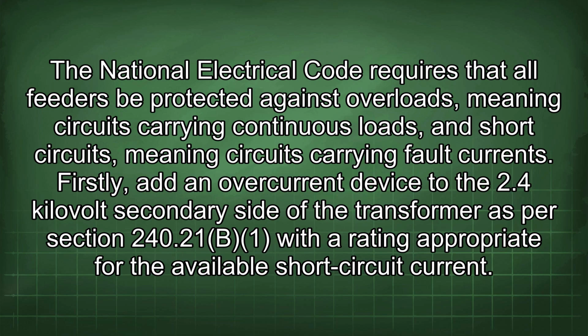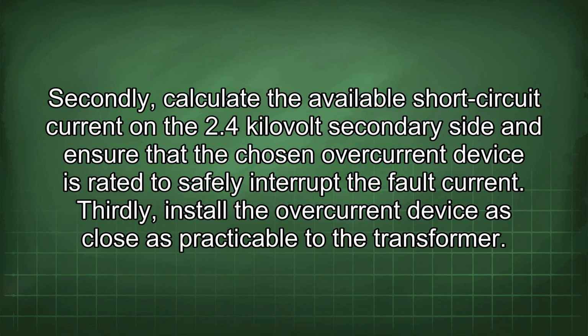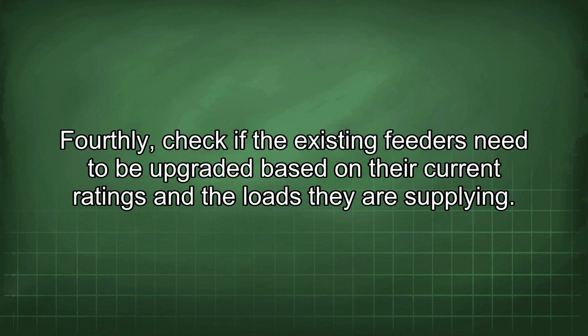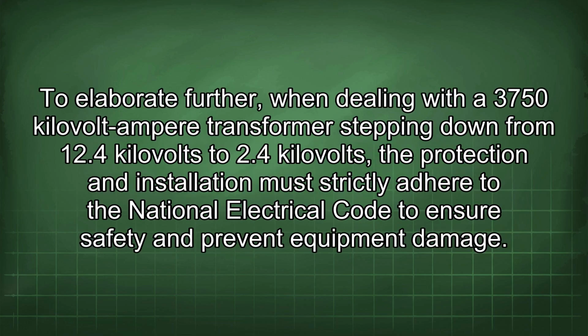Firstly, add an overcurrent device to the 2.4 kV secondary side of the transformer as per Section 240.21(B) with a rating appropriate for the available short circuit current. Secondly, calculate the available short circuit current on the 2.4 kV secondary side and ensure that the chosen overcurrent device is rated to safely interrupt the fault current. Thirdly, install the overcurrent device as close as practicable to the transformer. Fourthly, check if the existing feeders need to be upgraded based on their current ratings and the loads they are supplying.